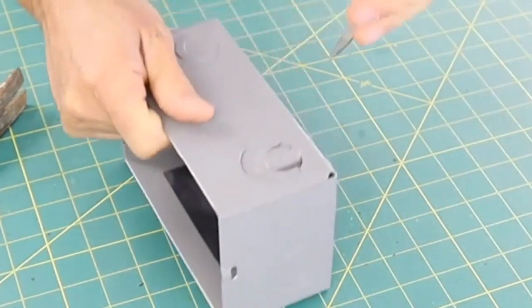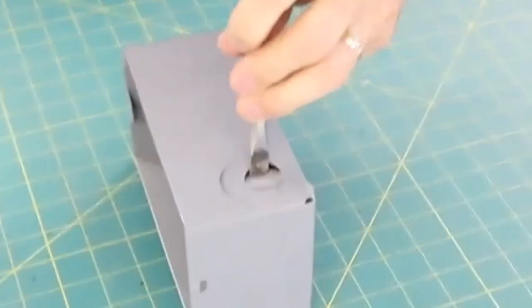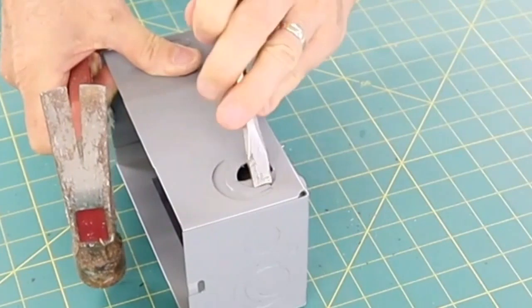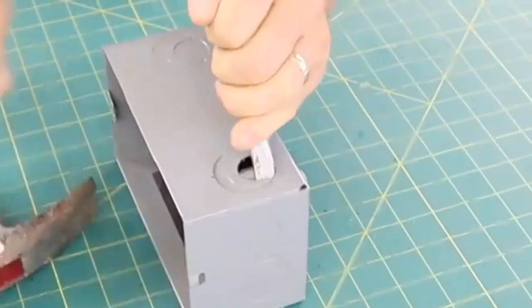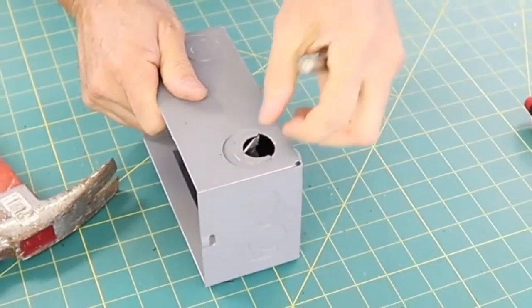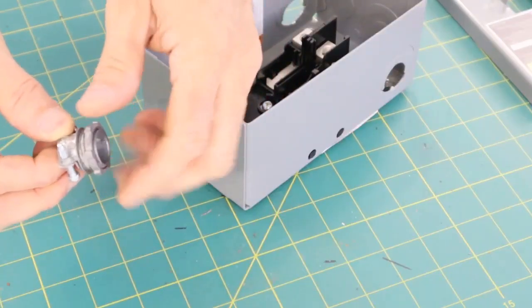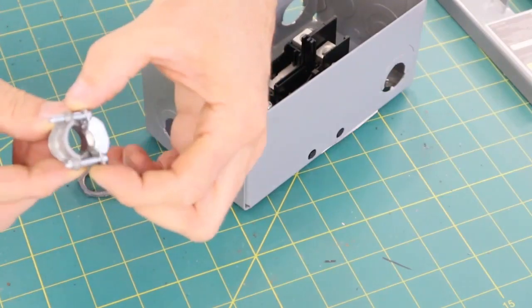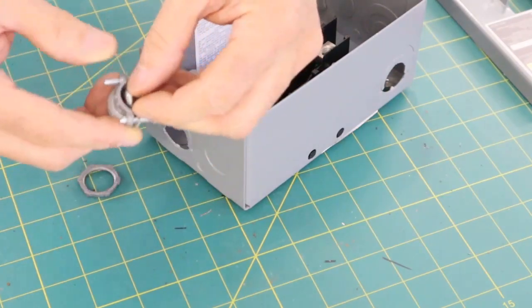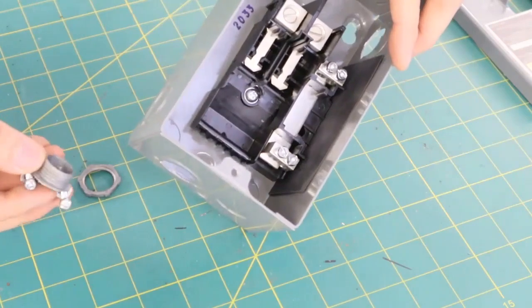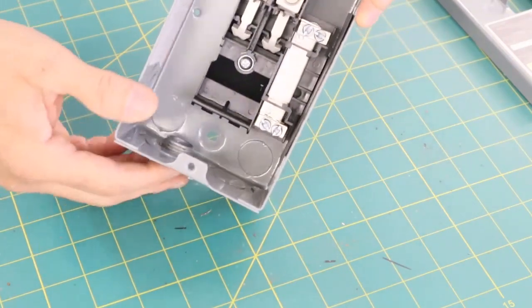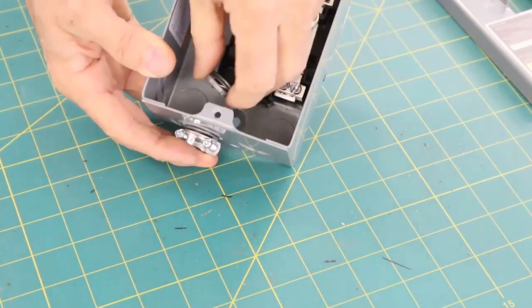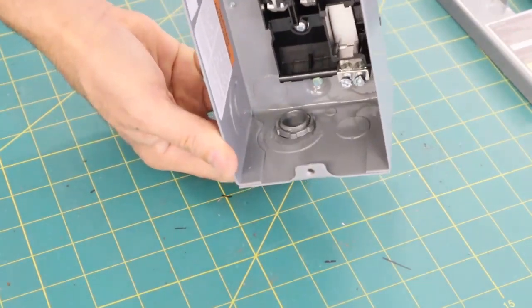In order to get the wires from the outside of the box to the inside of the box, I had to knock out three plugs on the outside of the box. There's two metal plugs at the top I had to knock out and one plug at the bottom. Once the plugs are knocked out of the box, then I can install strain relief clamps in each hole. These clamps clamp down on the wire to make sure the weight of the wire is not pulling on each connection.